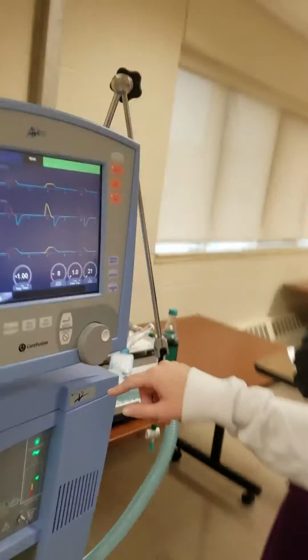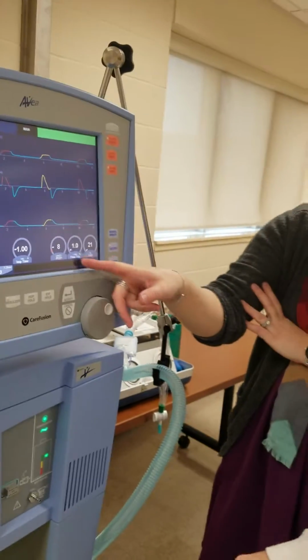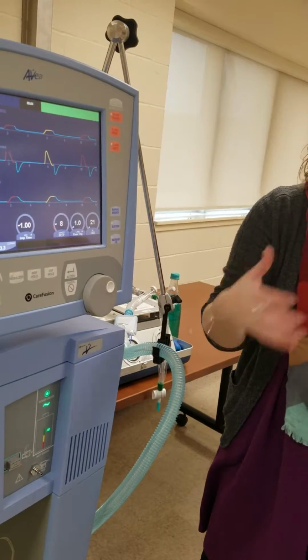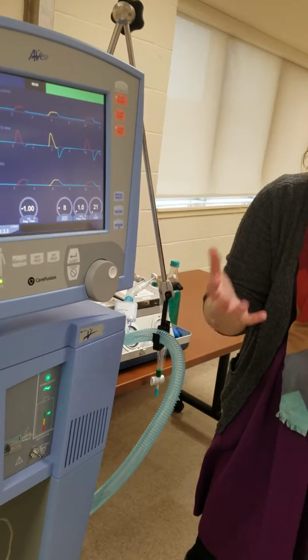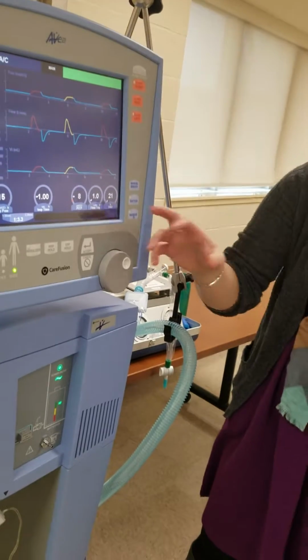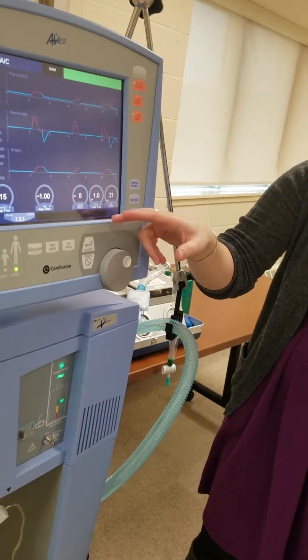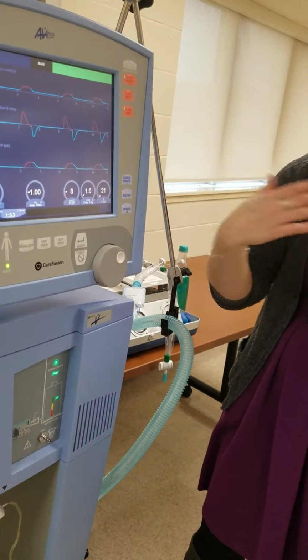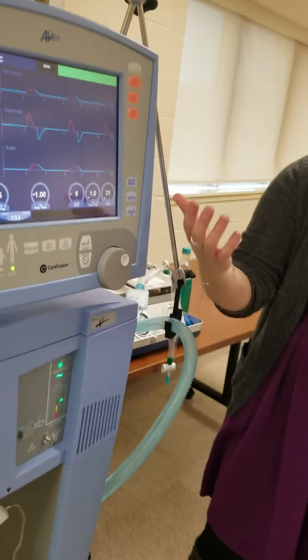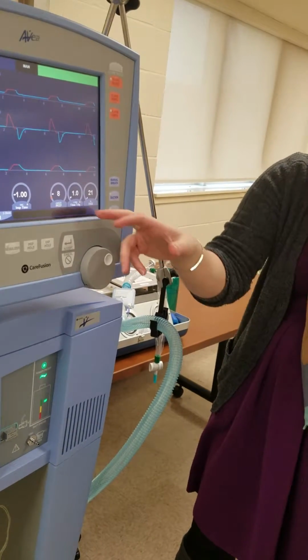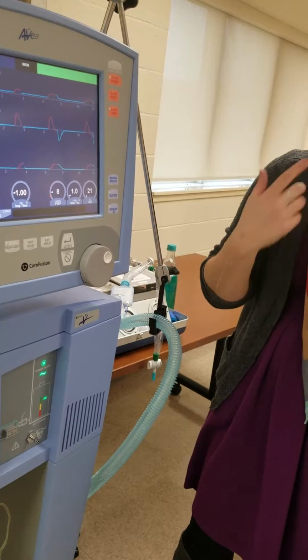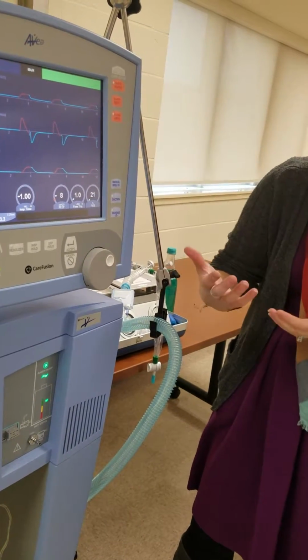Put this little cup in. And the flow triggering, so anytime you hear the word trigger, that's something that triggers a breath, something that will start a breath. So in this ventilator, in this mode, it's the flow, how much flow the patient pulls through that tube to get it to trigger a breath. So he's got to pull a whole liter worth of air to get it to trigger a breath.